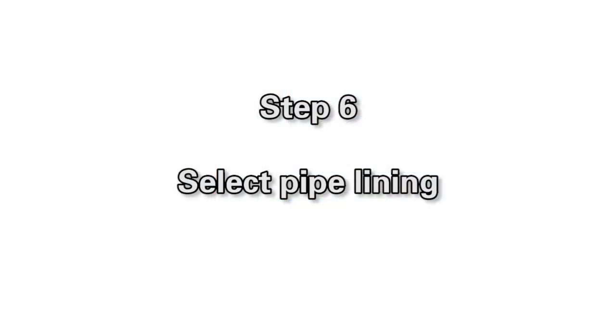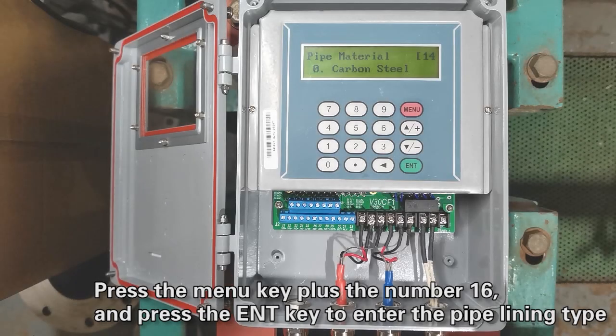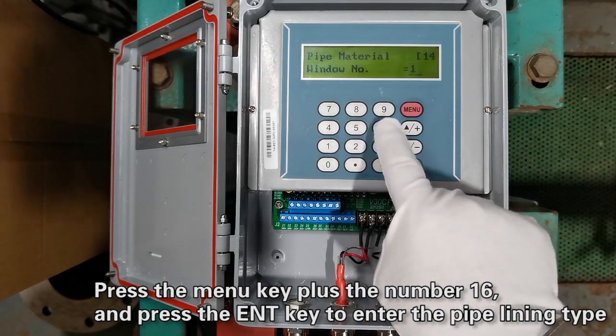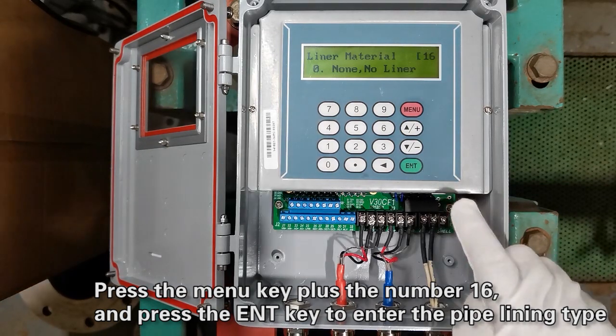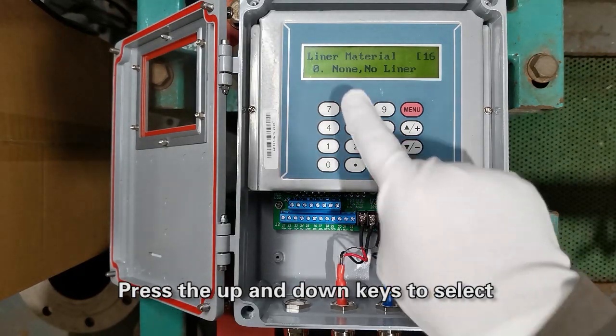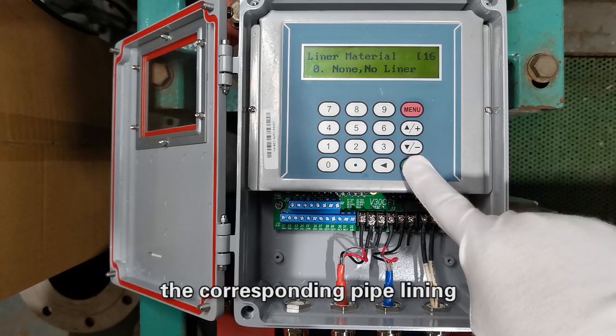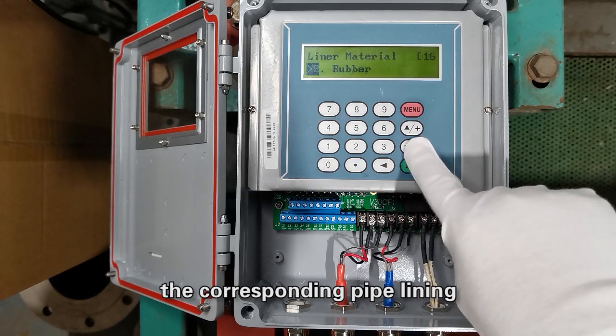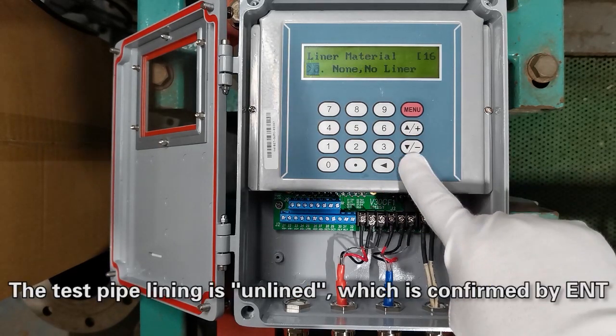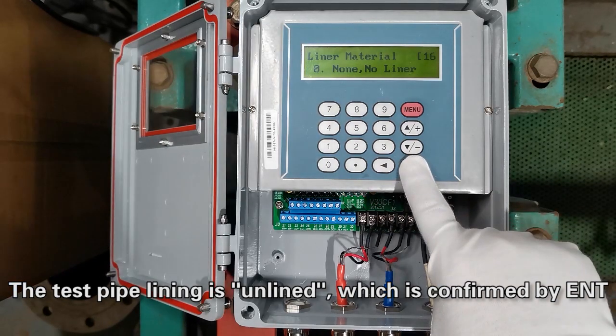Step 6. Select pipe lining. Press the menu key plus the number 16 and press the Enter key to enter the pipe lining type. Press the up and down keys to select the corresponding pipe lining. The test pipe lining is unlined, which is confirmed by Enter.